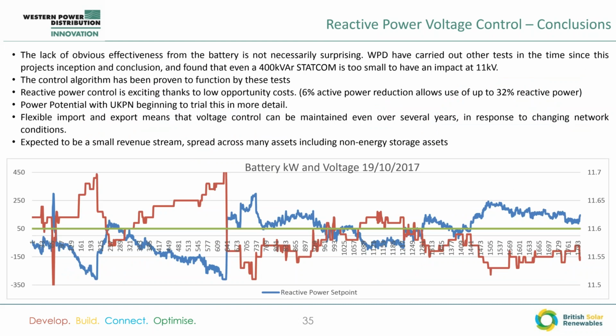I've reported some of this back to WPD throughout the process, and independently they've been doing some other tests on reactive power, and they found that a 400 kVAR StatCom wasn't really having an impact at 11 kV. So the fact that our smaller battery wasn't having an obvious impact was not particularly surprising.